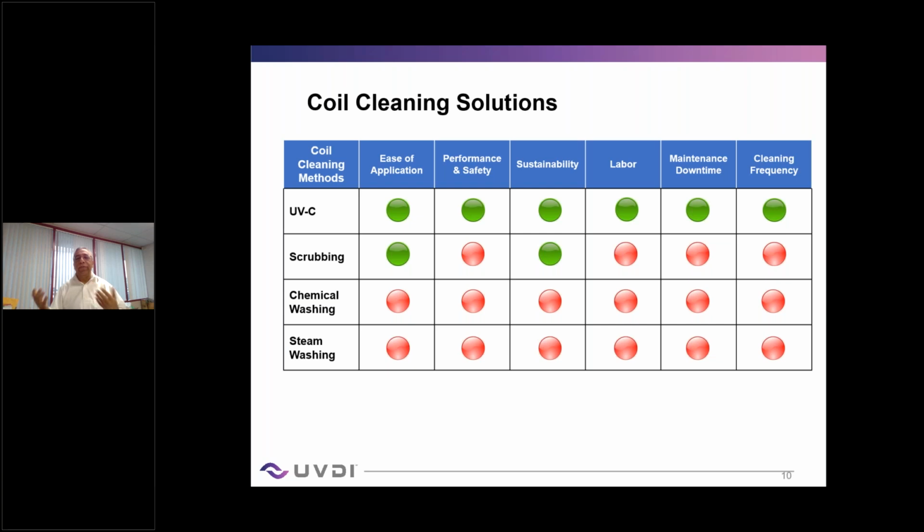So today, most of the time, people are just cleaning it maybe twice a year or maybe a little bit more. The problem is that these biofilms are very stubborn. You just need one CFU or just a few colony counts to remain, and then when the cleaning is over and they get back into that environment, they start growing back rapidly again. So it kind of defeats the purpose, and your energy impact starts getting affected right after that cleaning.